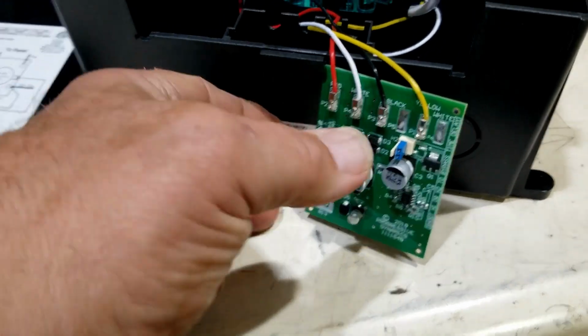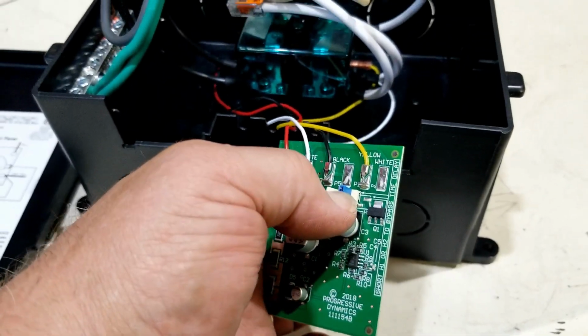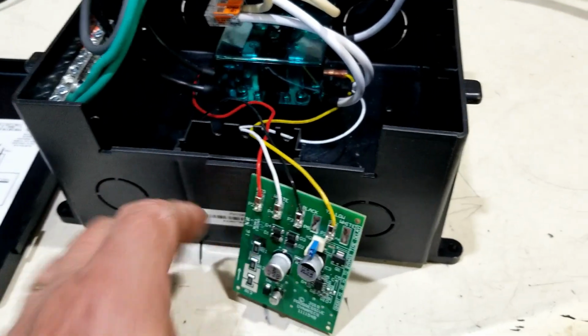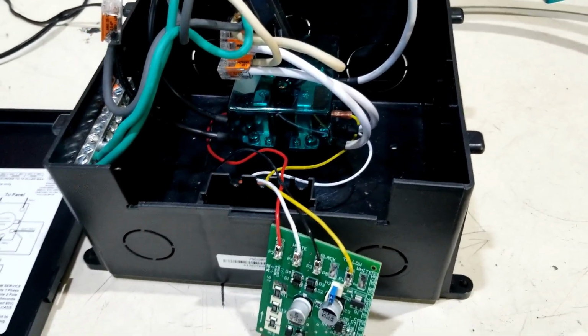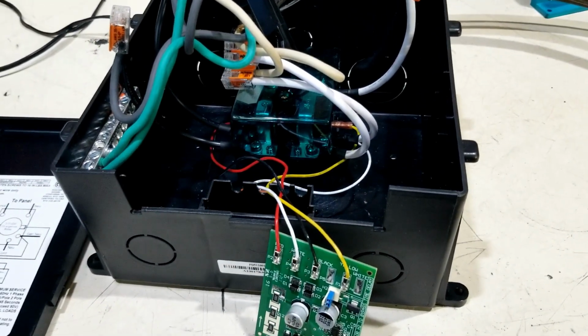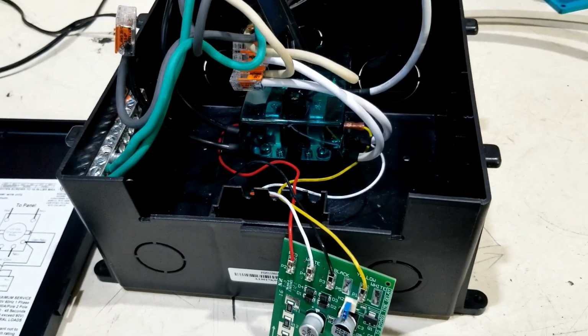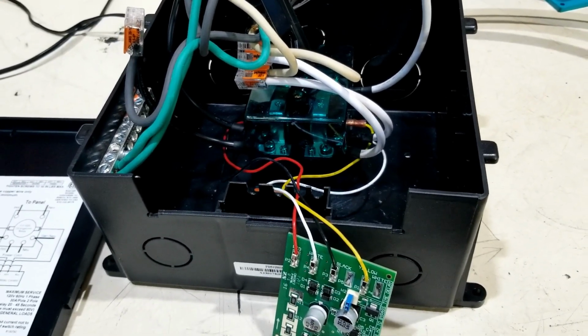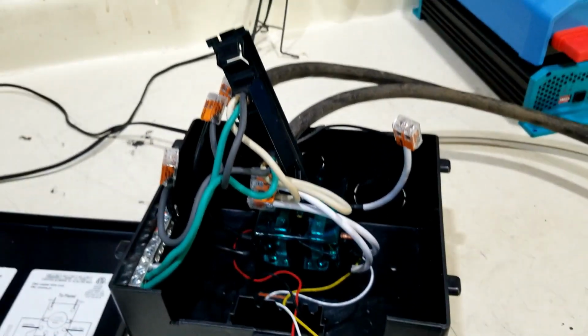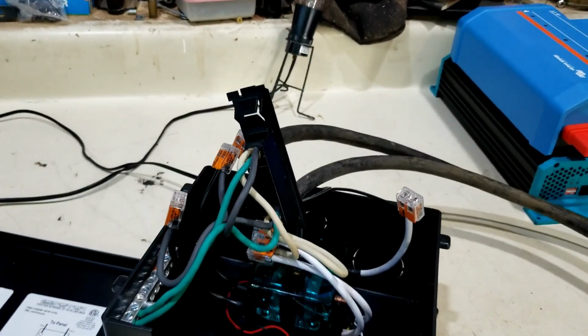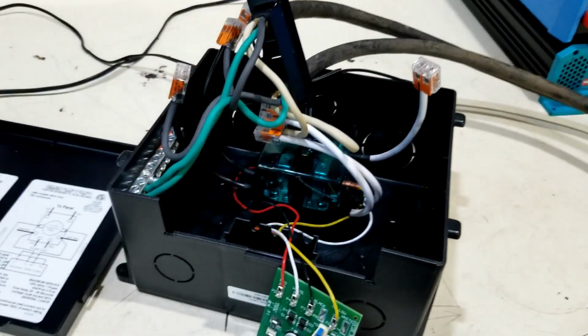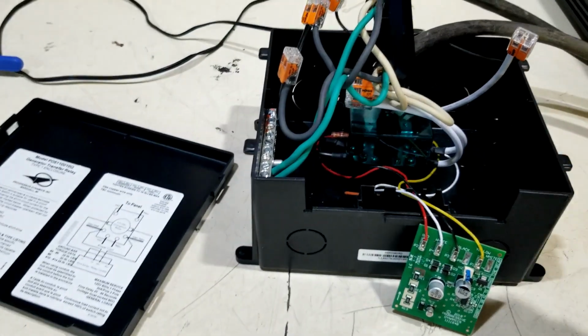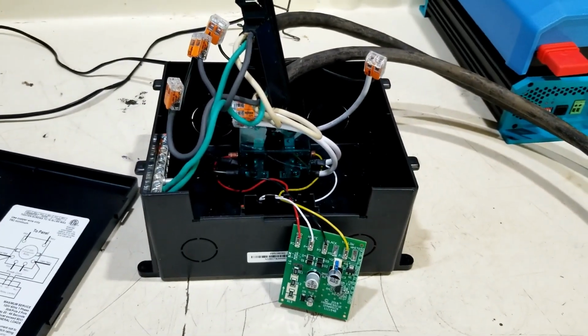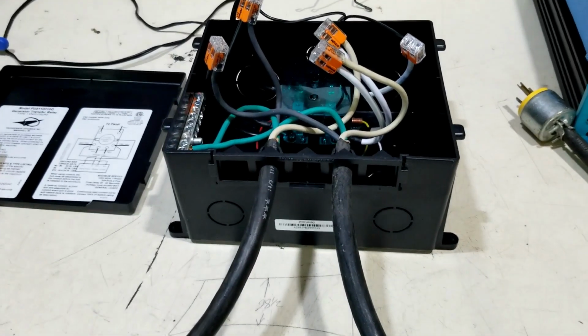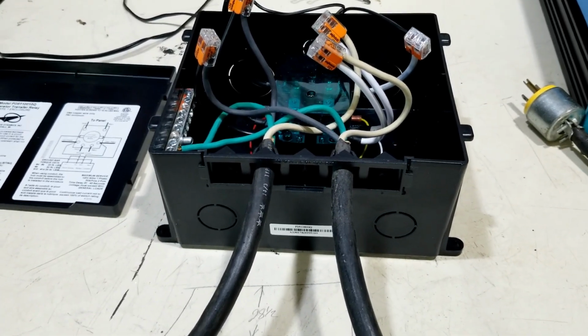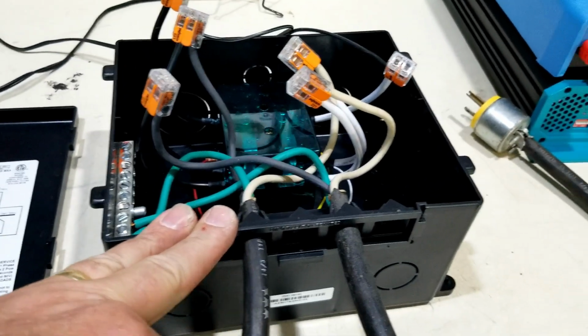So I'm going to leave this jumper on and get rid of that time delay so that as soon as I lose shore power, within just a couple of milliseconds, my transfer switch is going to automatically change from shore power over to inverter power. With that time delay circuit disabled, I put everything back together.